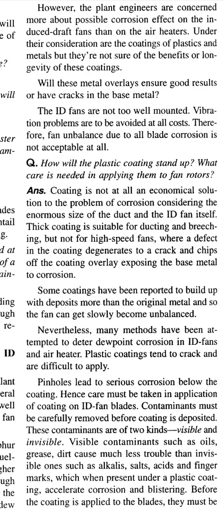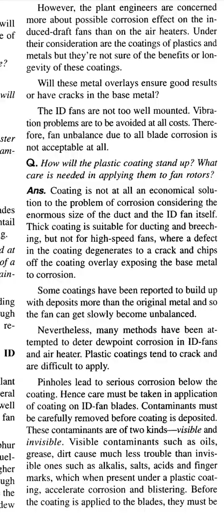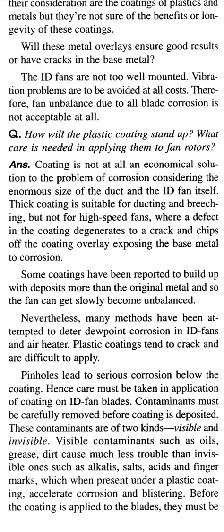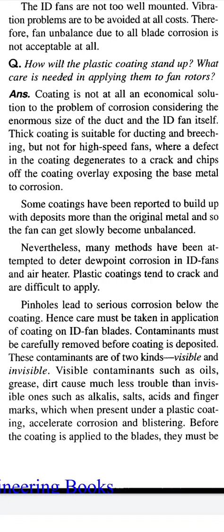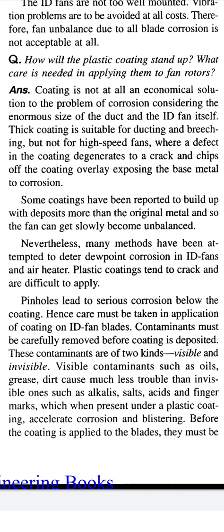Answer: coating is not at all an economical solution to the problem of corrosion considering the enormous size of the duct and ID fan itself. Thick coating is suitable for ducting and breeching but not for high speed fans, where a defect in the coating degenerates to a crack and chips off the coating overlay, exposing the base metal to corrosion. Some coatings have been reported to build up with deposits more than the original metal, and so they can slowly become unbalanced.